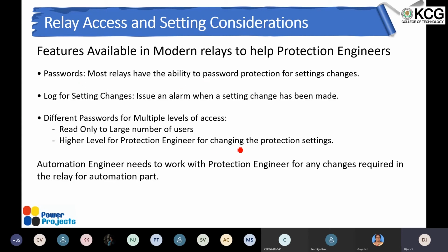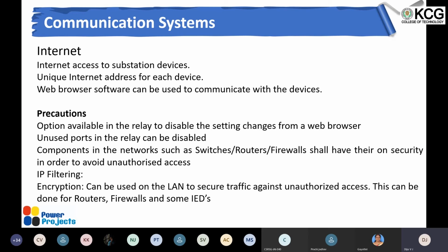So in the industry, what we generally follow is that the automation engineer or the SCADA engineer or the operation engineer should discuss with the protection engineer any changes required in the relay, even though it's an automation part of the change. So the protection engineer is considered the custodian of the protection relay. That's how, at the industry level, we are able to manage the cybersecurity issues. And the communication systems of the various relays, or what we call IEDs, intelligent electronic devices.